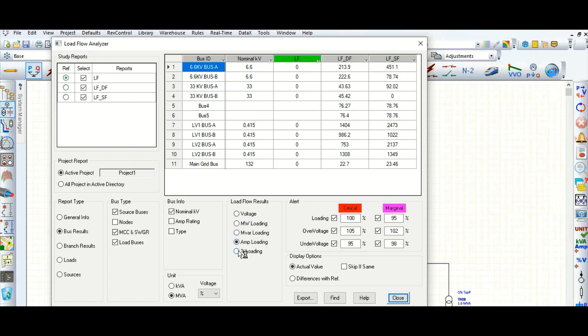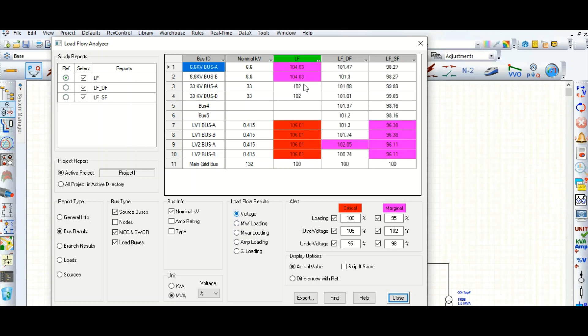At a glance you can check the bus voltage. For the 6.6 kV bus A, in no load configuration it is 104.03% voltage — this is in percentage value, which you can also switch to absolute value. In dual feed configuration it is 101.47%, and in single feed configuration it is 98.27%. You can compare this data on a single page.